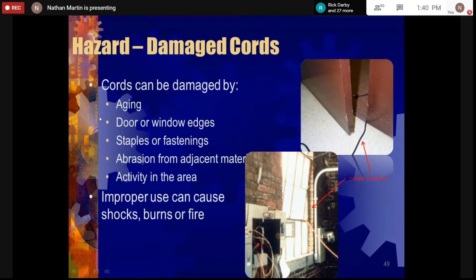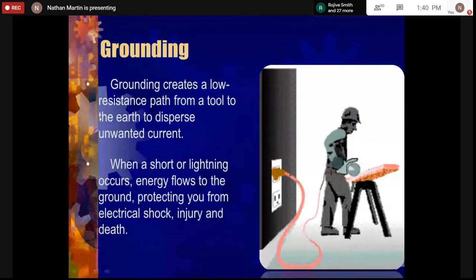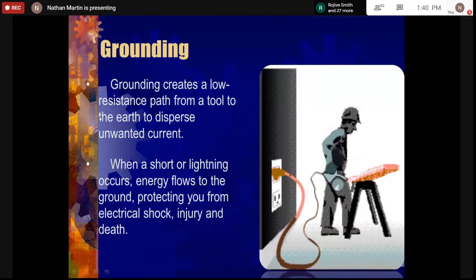Grounding - a lot of us are guilty of this. When we buy our power tools and it comes with a ground pin, most of the time persons tend to remove the ground pin because they want to plug it into a 2-prong socket outlet. Students, if you don't have any ground, most of the time the breaker will not trip. You need your ground or earth for your high current to flow so that your breakers can trip. You need the ground in the installation - it's basically one of the most important conductors in an installation.